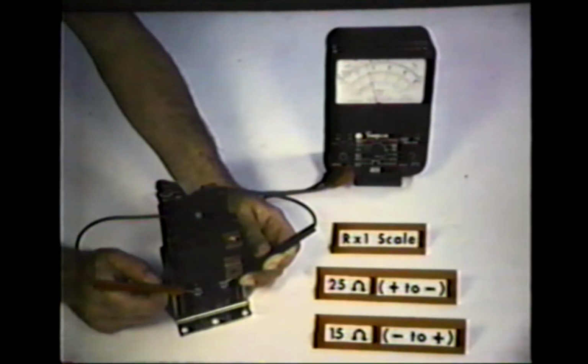The forward and reverse contactor coils can be checked on the R×1 scale. The meter should read approximately 25 ohms in one direction and 15 ohms in the other because of the suppression diode mounted internally in the coil.